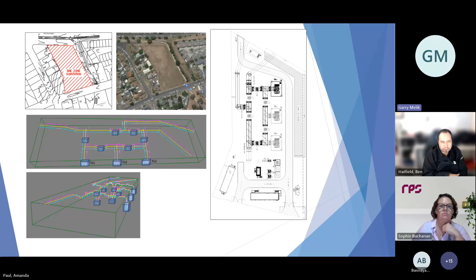This slide shows the first stage of the substation development, where it will be fitted with only one transformer, shown here as a double circle. The substation will be connected to two power lines: one supplying current into the substation, and the other taking part of the supplied current further along the transmission network, feeding another zone substation.